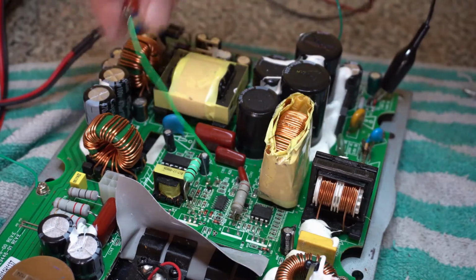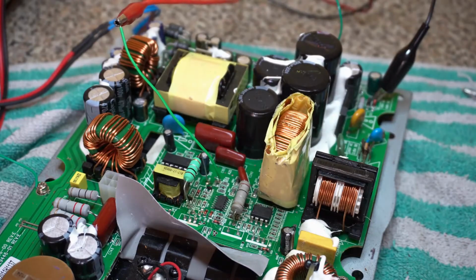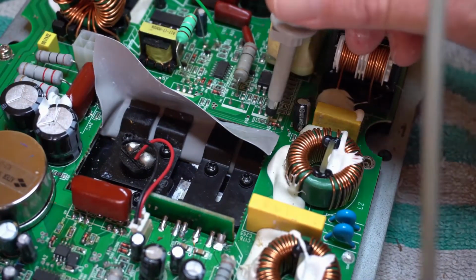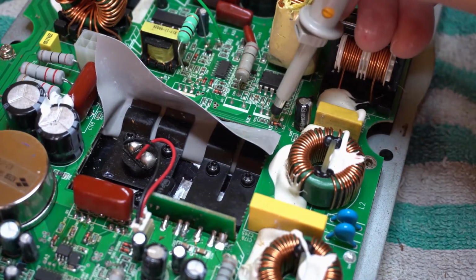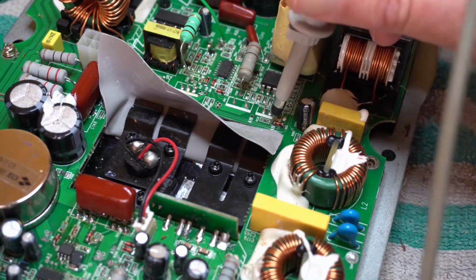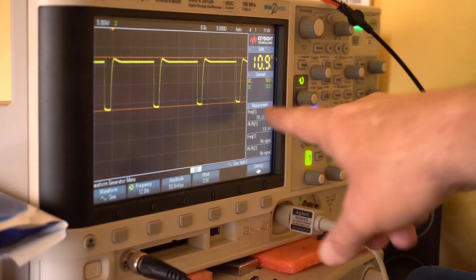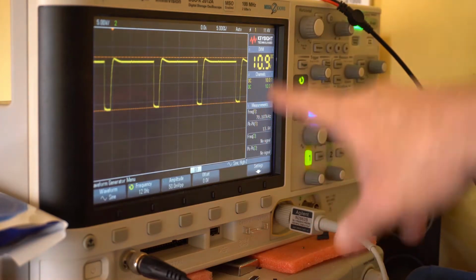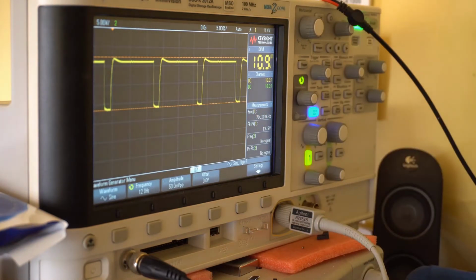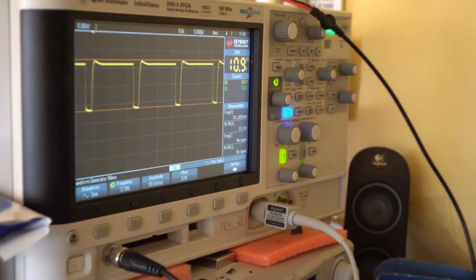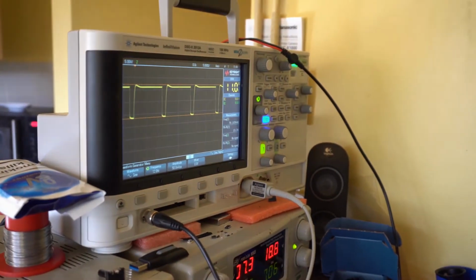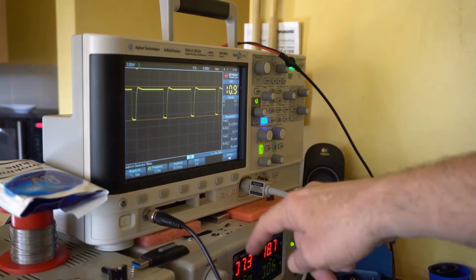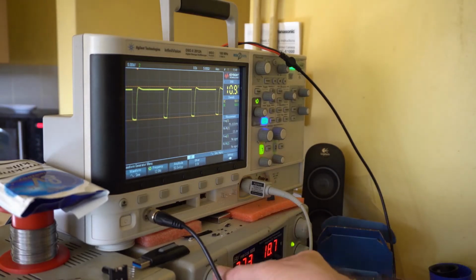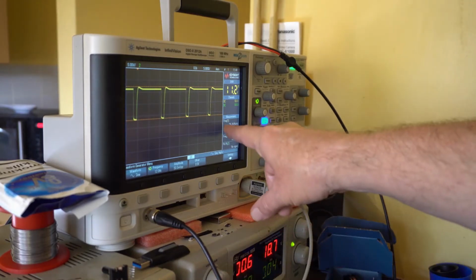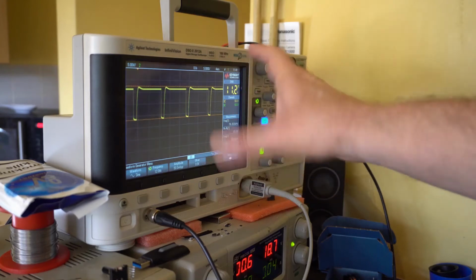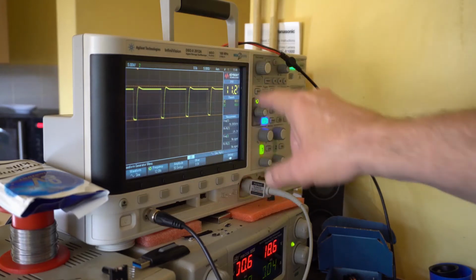So I've powered this up to 7 volts, and now if I probe this PFC circuit again - it was running at 79 kilohertz, it's now running at 70. So it's a touch fast, but it doesn't matter. If I turn the 7 volts off, you can see it jumps back up to 79, or 80, 84 kilohertz for the PFC - doesn't matter. But when that switch mode power supply comes in, the PFC must synchronize with it.